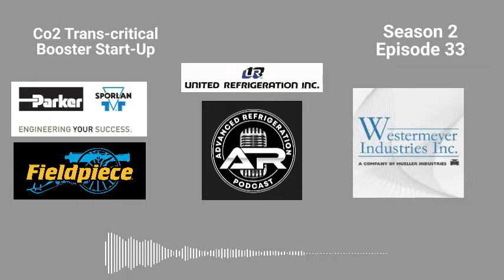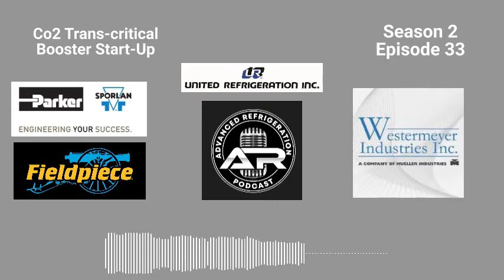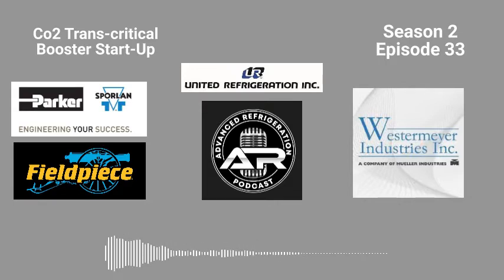You're going to remove the reliefs, and you're going to pressurize the gas cooler up to whatever the customer says. I usually go 1,900 pounds. I go right under what the reliefs on the compressors are for. So if the reliefs on the compressors are, say, 2,000 pounds or 1,900 pounds, I'll go like 100 pounds under those because I'm not capping off the compressors. That's way too much work for another 100 pounds. I mean, if it's going to blow at 1,900, it's going to blow at 2,000.